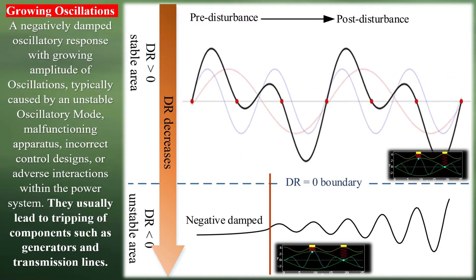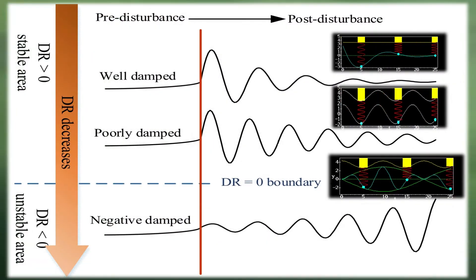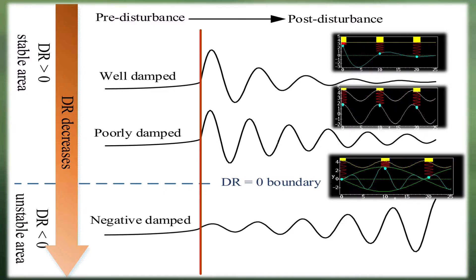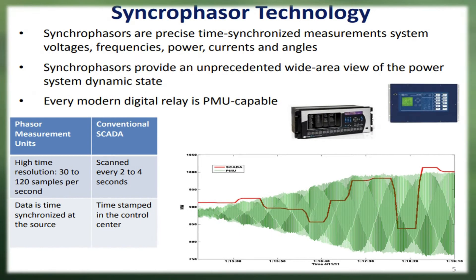Synchrophasor technology is the best tool to find power system oscillation. Synchrophasors are time-synchronized electrical measurements that represent both the magnitude and phase angle of electrical sinusoids. They are measured by fast time-stamped devices called phasor measurement units, or PMUs. PMUs are 100 times faster than traditional supervisory control and data acquisition, SCADA, systems. Synchrophasors constitute the basis of real-time monitoring and control actions in the electric grid, providing enhanced situational awareness capabilities with many applications in power systems.